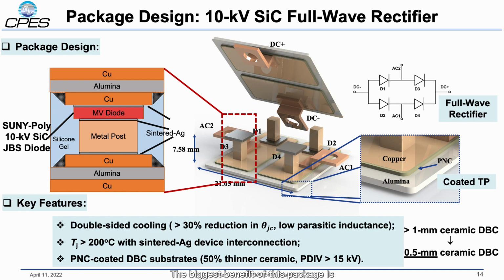The biggest benefit of this package is that we have PNC coated DBC substrates, which allow us to achieve PDIV higher than 15 kV with a much thinner ceramic, which means we will have lower thermal resistance and still have better insulation than the other medium voltage power modules.